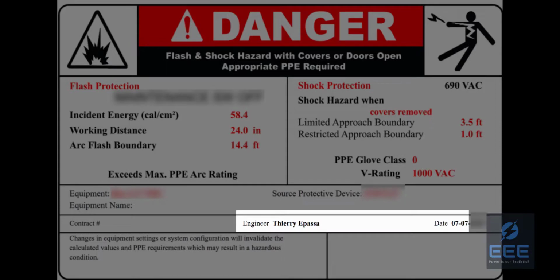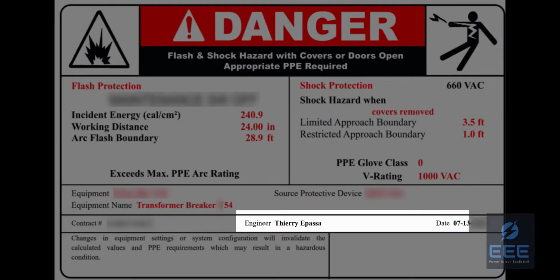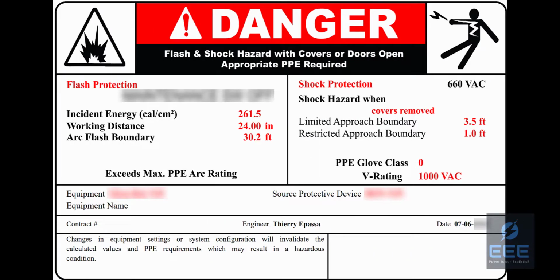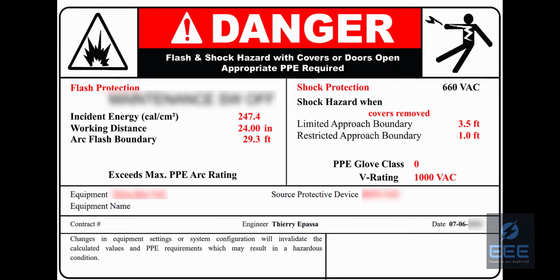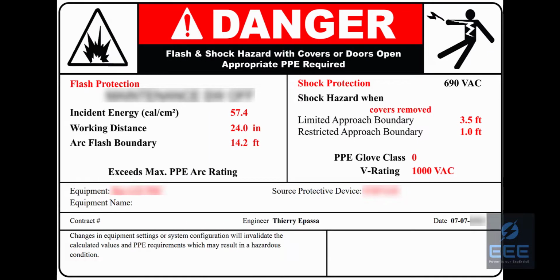In some facility, some engineer and technician told me they had a suspicion something was not correct. They just couldn't find the rules. I asked what made them suspicious. Some answers: we hired 3 engineering firms to do arc flash studies within 3 months for the same facility. Their results were all significantly different. Some sites had no idea their study was so incorrect.